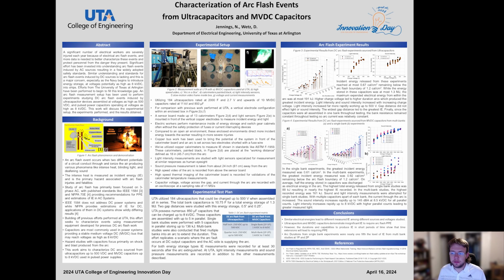For the single bank experiments, the greatest incident energy measured was 0.61 calories per centimeter squared. For the multi-bank experiments, it was 0.92 calories per centimeter squared. This all remained below 1.2 calories per centimeter squared. On average, half the energy stored within the capacitor bank overall was discharged into electrical energy in the arc.